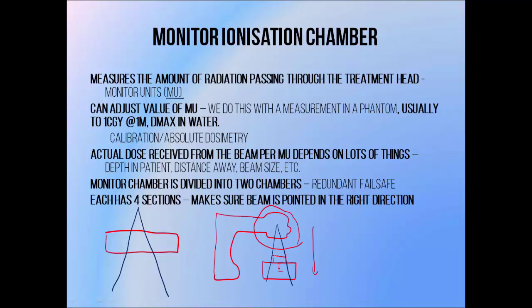In order to determine how much an MU is worth, we take a measurement inside a reference geometry. A popular choice is to do it 100 cm away from the radiation source at a depth of a few centimetres in water, which is regarded as equivalent to human tissue. We adjust the amount of radiation that comes out of the machine per monitor unit so that 100 monitor units deliver a dose of 1 grey — so 1 monitor unit is usually equal to 1 centigray. Setting this value is the process of beam calibration, or absolute dosimetry. We can adjust for any changes in conditions through a process known as relative dosimetry.